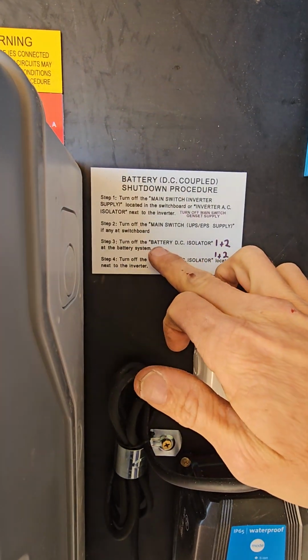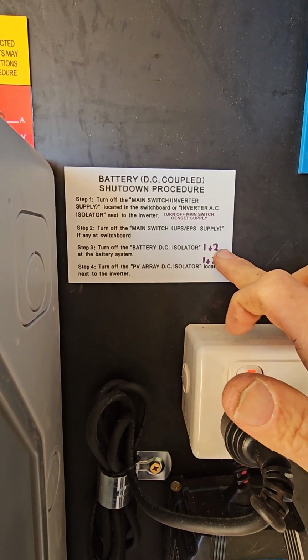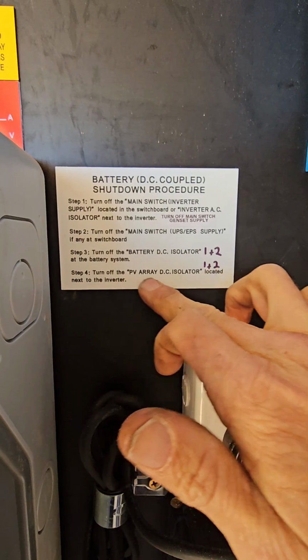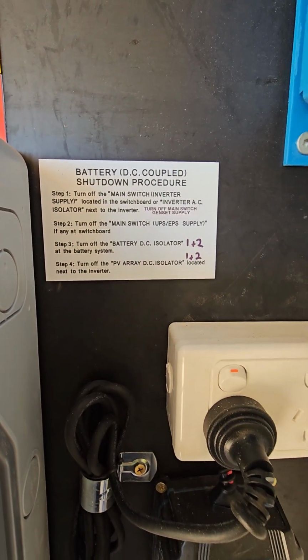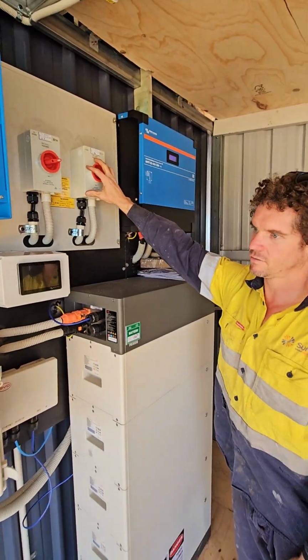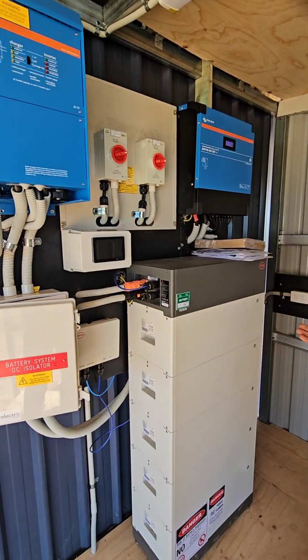So that's the last 2 steps: battery system DC isolator 1 and 2, we've turned them off. Turn off PV array DC isolator 1 and 2, which are these ones in the middle here. They're now off. Now your system is fully isolated.